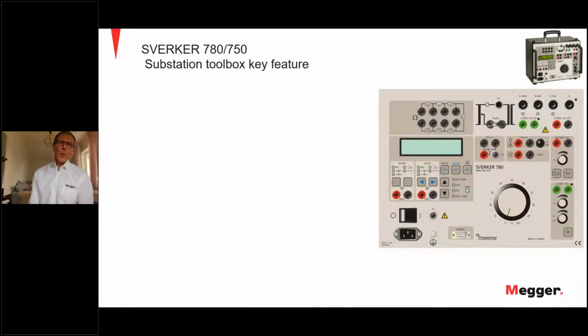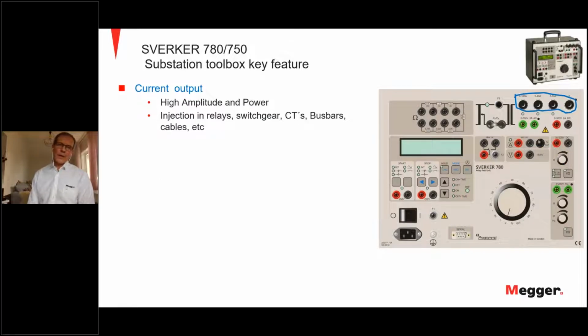And I will start to speak about the one-phase SVERKER, the SVERKER 780 and the SVERKER 750, which are used for testing substations, and it's not only for testing relay equipment, it's also used for doing other things in the substation. So that's why we are calling it the toolbox for the complete substation. And with the SVERKER 780 and 750, you have, of course, a current output, and it's only one current output, which is used for doing injection at high amplitudes, and it can give up to 250 amps, and it also has very good power, so we can go up to 800 VA.